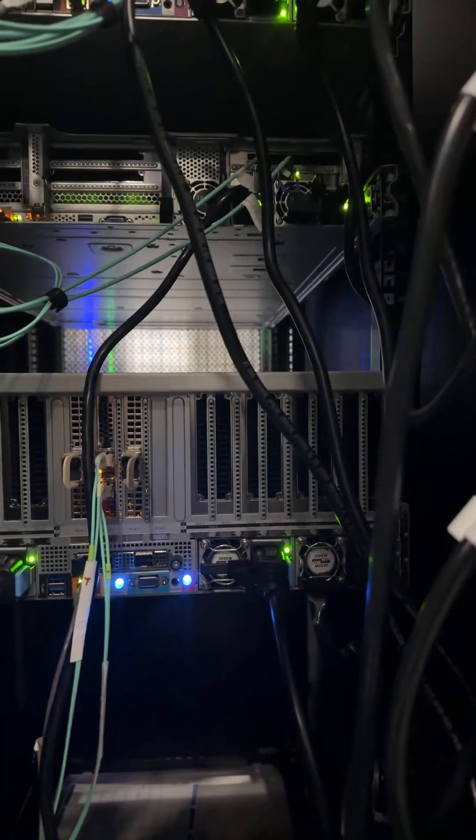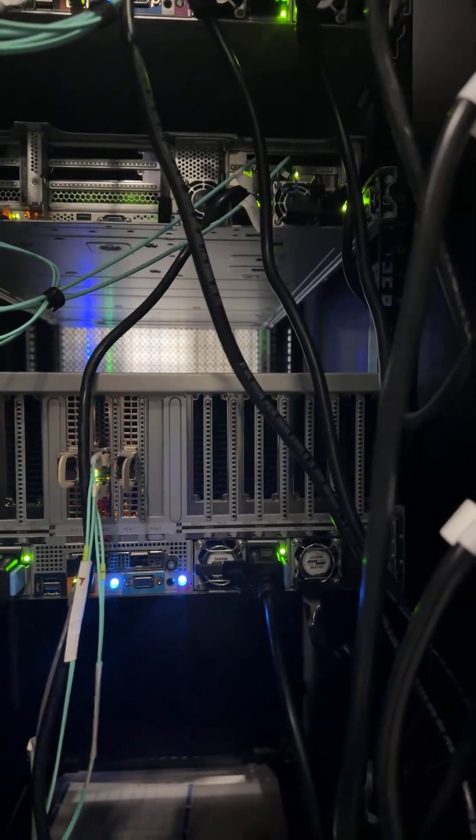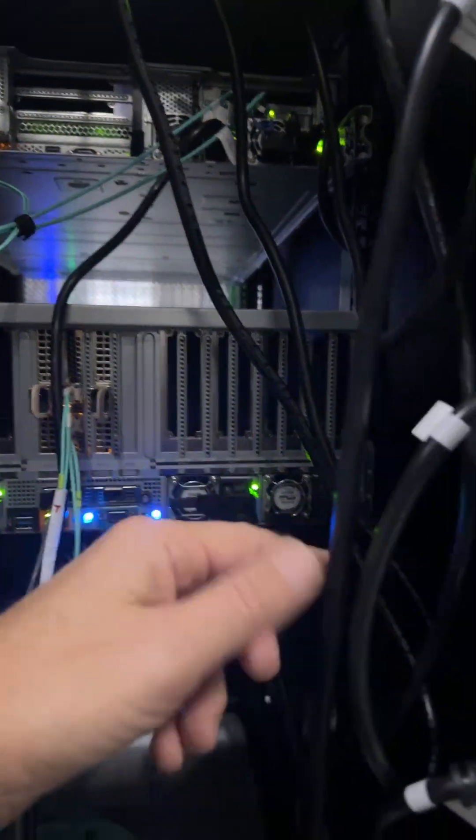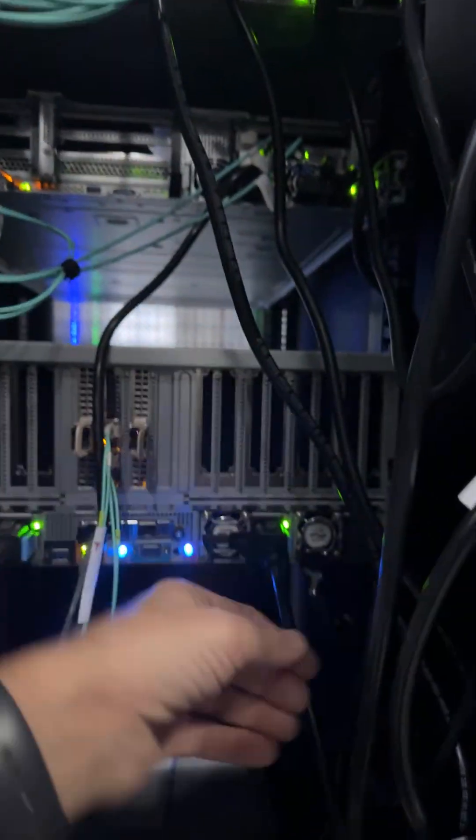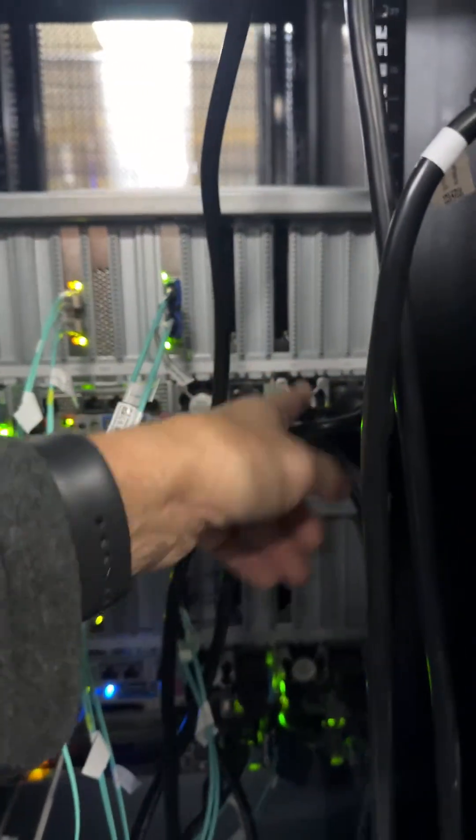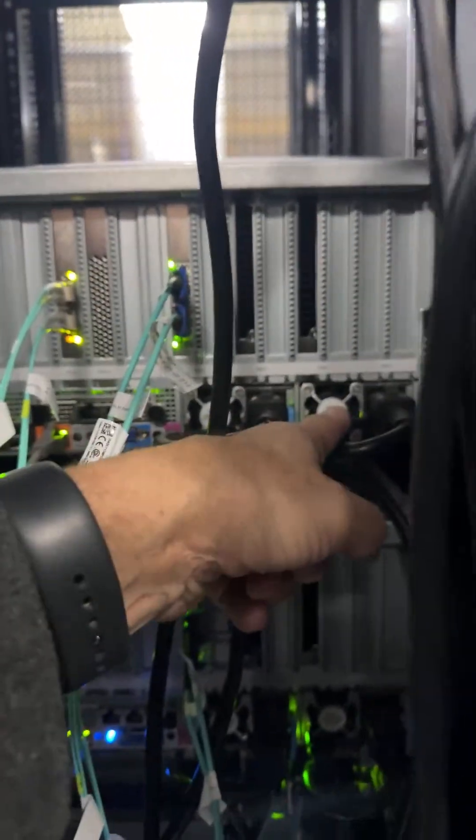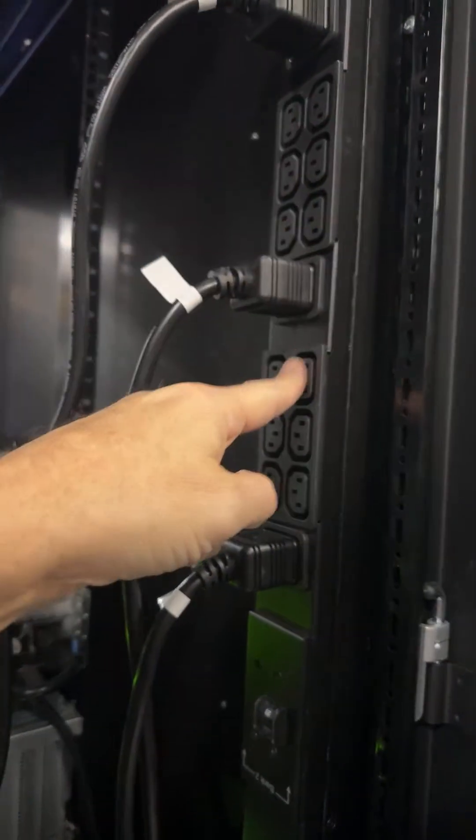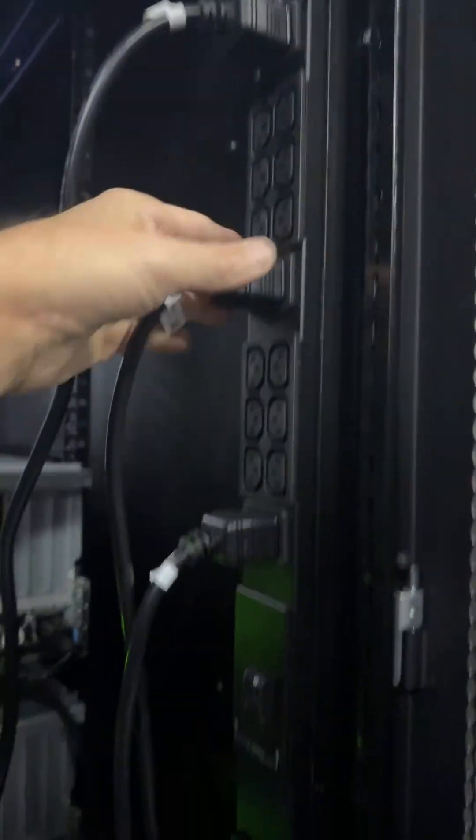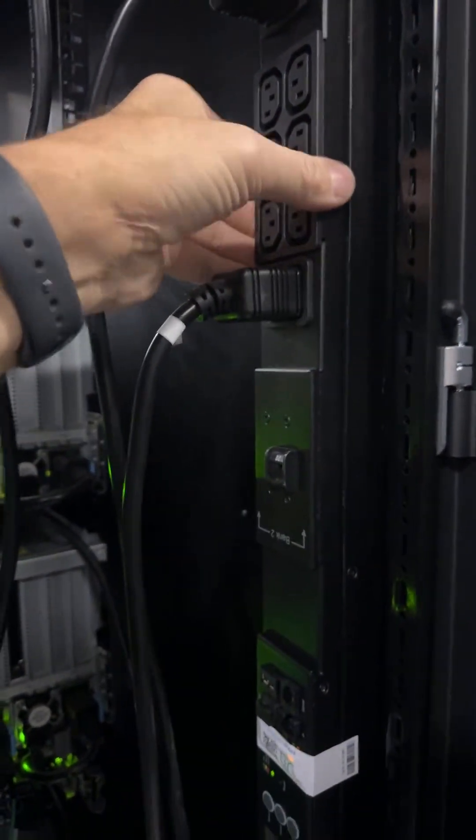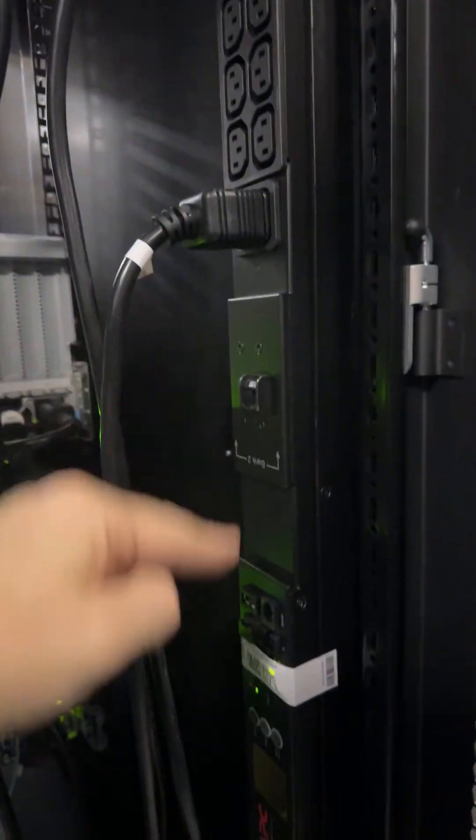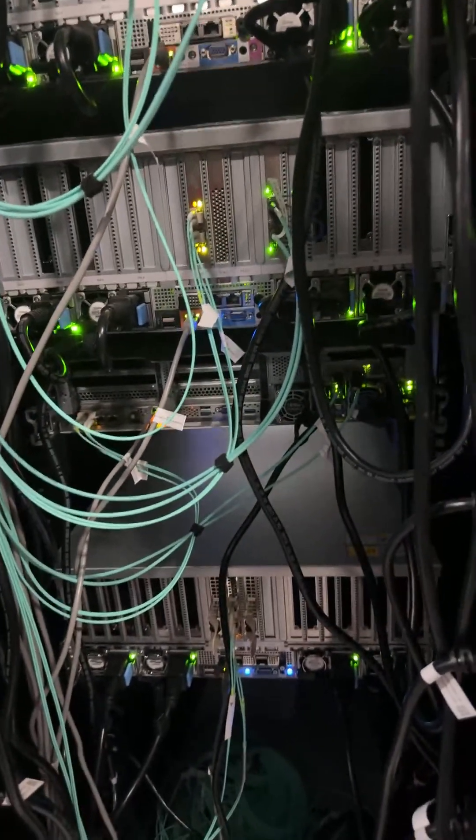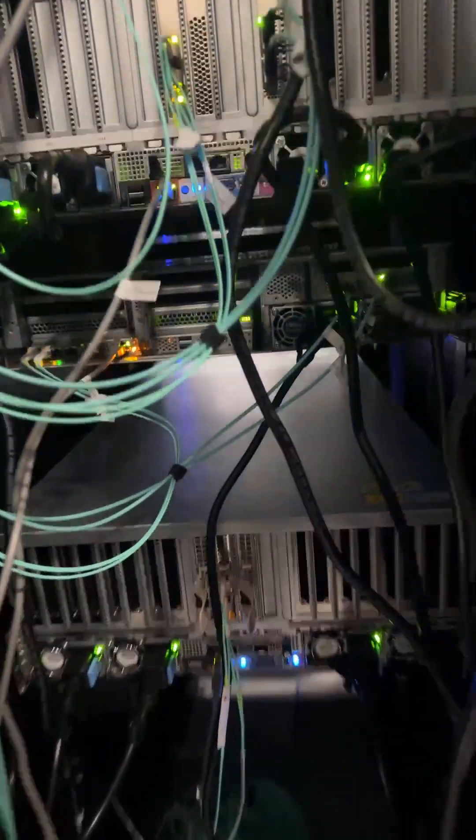So now we know it cannot be three servers at the same time, their power supply, the same one, it's not working. You follow what I'm saying? So that tells me it cannot be the cable and it cannot be all three servers or all three power supplies. So this one, this is called a PDU - so this is the issue, this is the culprit. So this one we need to have it replaced. APC, that's the model.